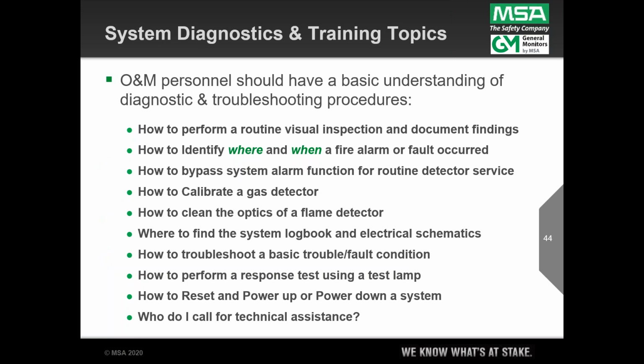I was a trainer, I still am a trainer. So we should have a training program for our technicians and our process engineers, everyone involved with the system: how to perform a visual inspection, document the findings, how to identify when and where a fire or fault has occurred, as well as a gas alarm, how to bypass the system if we need to do some work on it, how to calibrate a detector, how to clean the optics of a detector, how to find the logbook and schematics, how to troubleshoot a basic fault or trouble condition, how to perform a response test using a test lamp, how to reset or power up or power down that system, and who do I call if I need help.